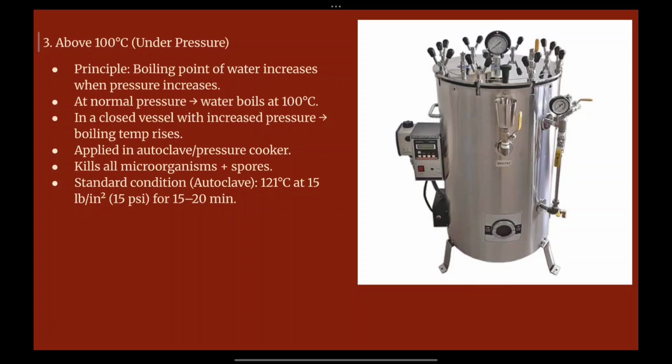So this steam travels through the autoclave, creates a pressure, and at this pressure the steam travels through the articles and kills all the microorganisms or spores that are present on them, and the steam is going to sterilize the materials. So the standard condition is also given. So this covers above 100 degrees Celsius. We'll be studying about autoclave in another video because it's complex. It involves a detailed understanding.